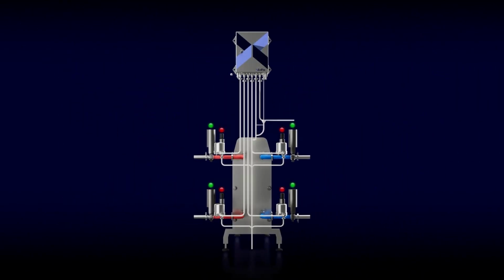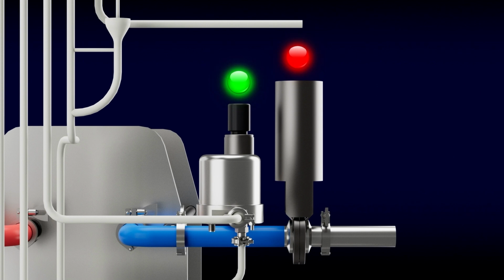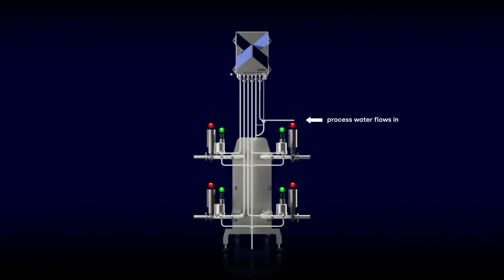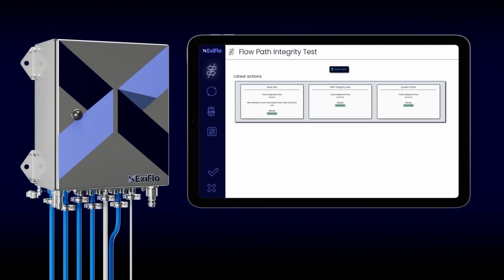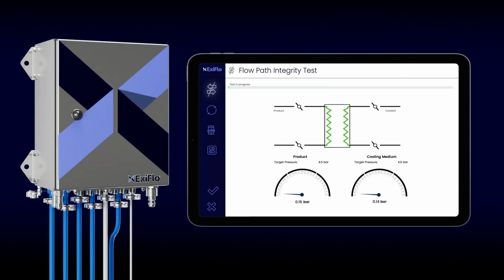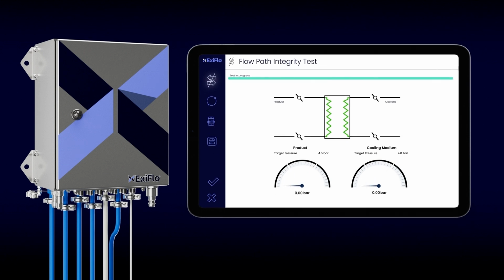When a test is performed, the heat exchanger is isolated from the system. Your process water then flows into Exiflo, and the plates are pressurized to normal operating conditions without the use of any other mediums. Exiflo consists of an innovative, patent-pending, electronically controlled fluid management system, accurately detecting flow rate across the channels and to the environment.